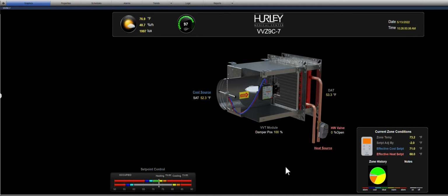What we don't know yet is what the relative humidity is in the space, because we don't yet have our VOC and relative humidity sensors at our two locations on each floor in the hallway. This will give us an indication of comfort load. If the relative humidity is above 50% or 55%, it creates an atmosphere that allows diminished evaporative cooling of sweat. So we try to keep it at 55% or below. Usually we try to keep it below 50% in the summer, but it's tough depending on the workload of people as well as the building envelope.